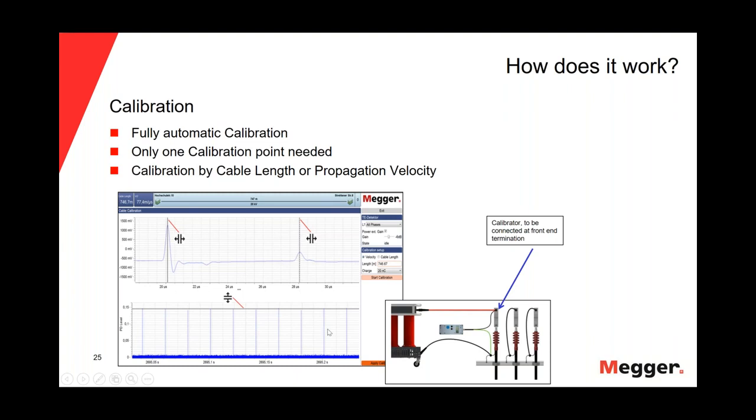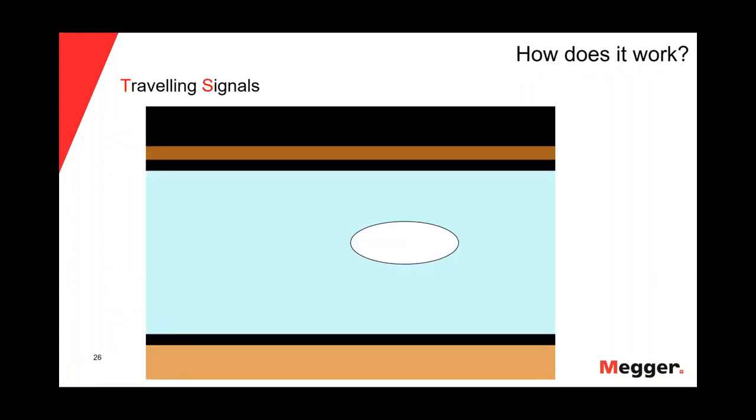Then during the calibration, we will have two pulses, the first one and the second one, okay? And this principle is the same that we will use to localize the partial discharge. We have, let's say, an air bubble inside of the insulation of a cable. So we will have the partial discharge. The energy will be split in two. Part of the energy will go straight to the beginning of the cable, to the coupling capacitor.